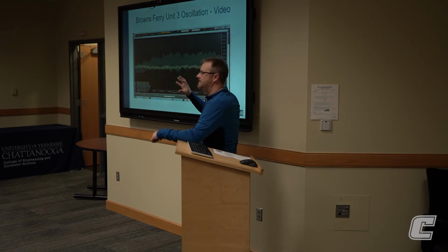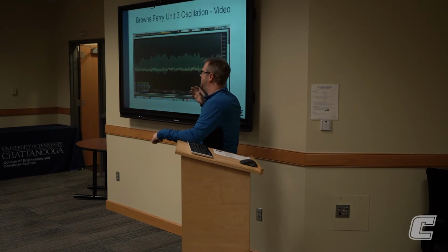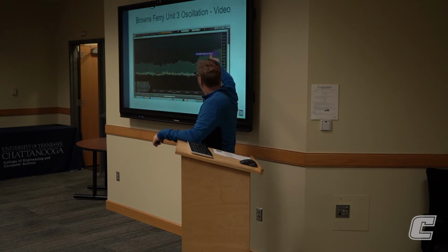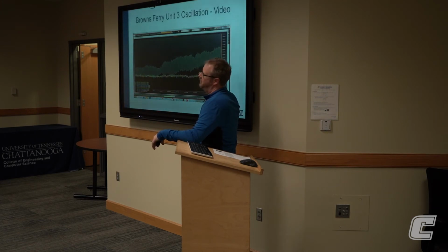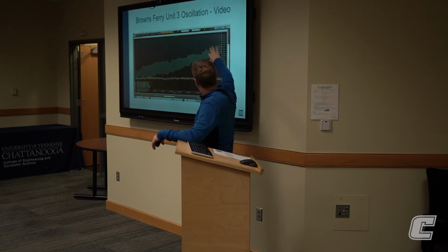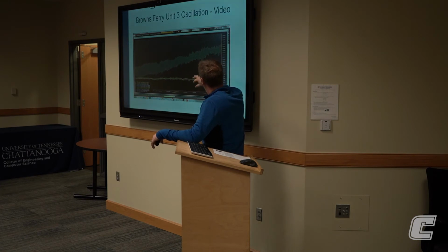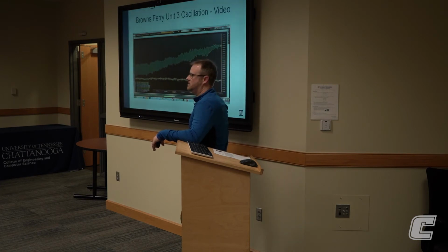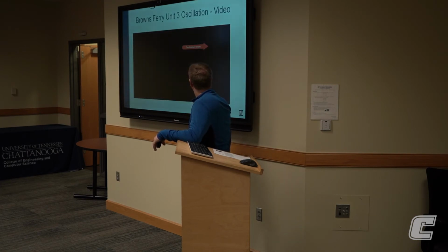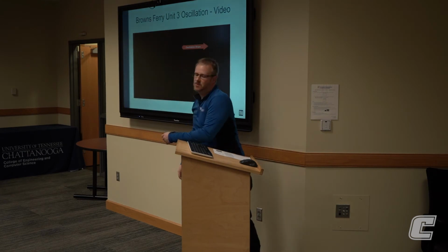And again, this is not good because what it relates to is that torsional stress on the rotor shaft. So this is 30 megawatts peak to peak. That's not good. Especially for long durations of time. But as they raise it up, can you tell if you look at the boundary, the envelope of the signature, it's going down, and then it stopped. So we knew something was going on.